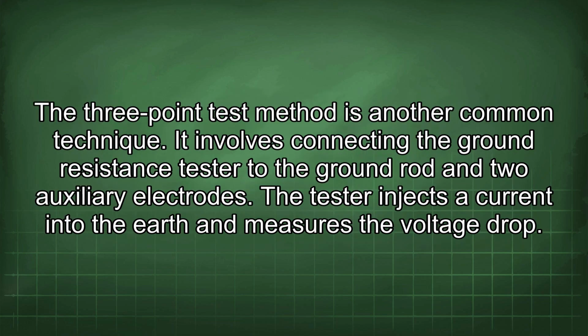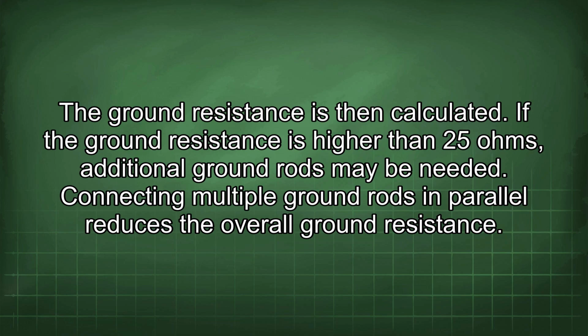The 3-point test method is another common technique. It involves connecting the ground resistance tester to the ground rod and two auxiliary electrodes. The tester injects a current into the earth and measures the voltage drop. The ground resistance is then calculated. If the ground resistance is higher than 25 ohms, additional ground rods may be needed.